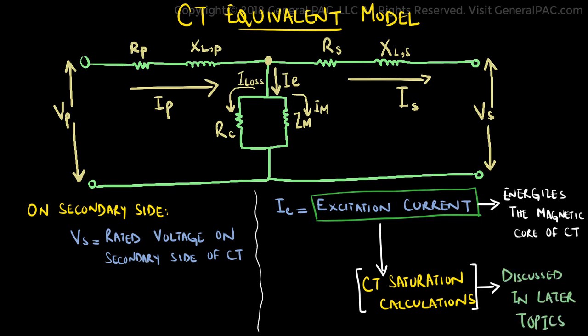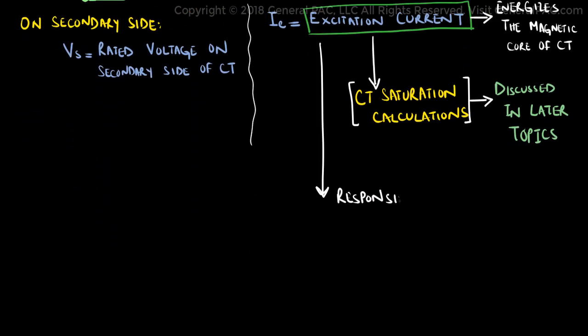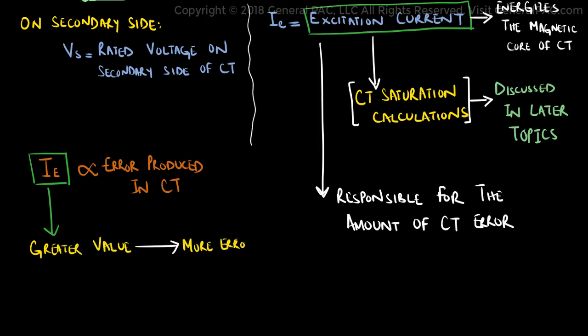Furthermore, this excitation current quantifies the amount of CT error which is present in the circuit. The greater the value of IE, the more error being produced in the current transformer, and vice versa.